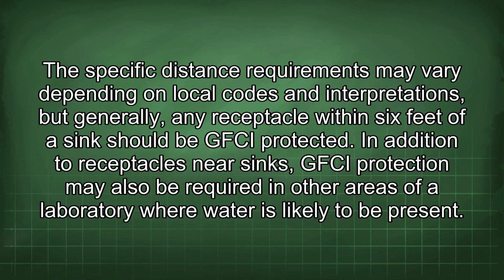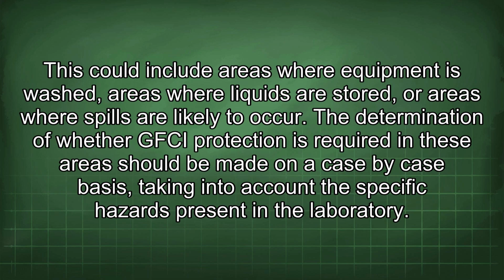In addition to receptacles near sinks, GFCI protection may also be required in other areas of a laboratory where water is likely to be present. This could include areas where equipment is washed, areas where liquids are stored, or areas where spills are likely to occur. The determination of whether GFCI protection is required in these areas should be made on a case-by-case basis, taking into account the specific hazards present in the laboratory.